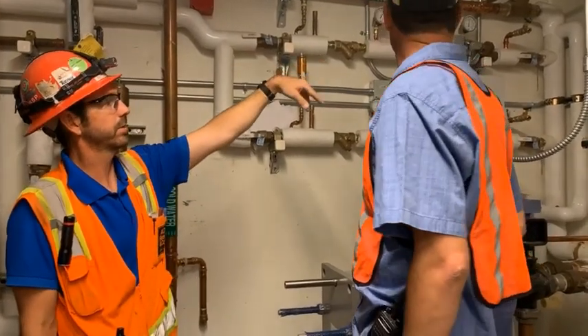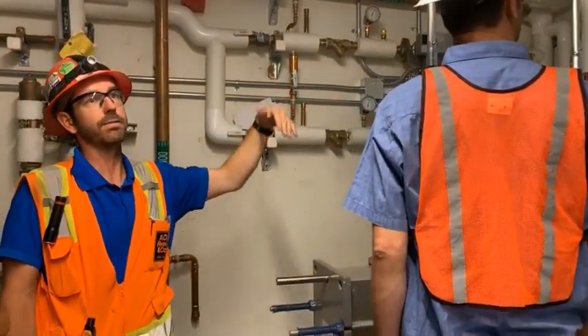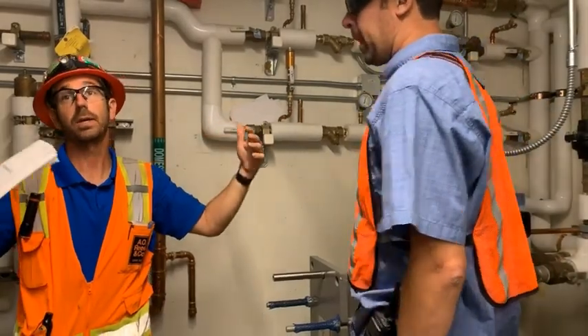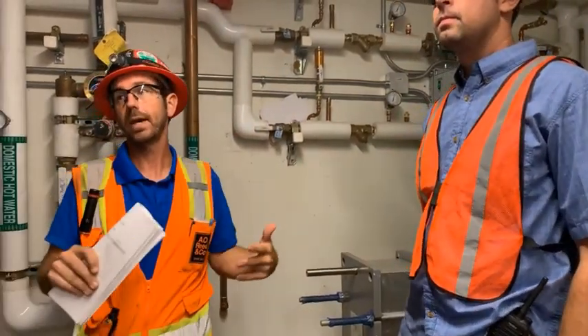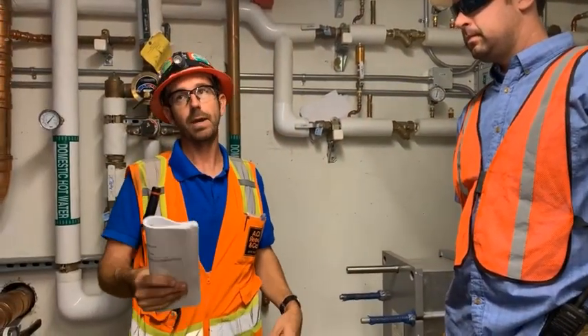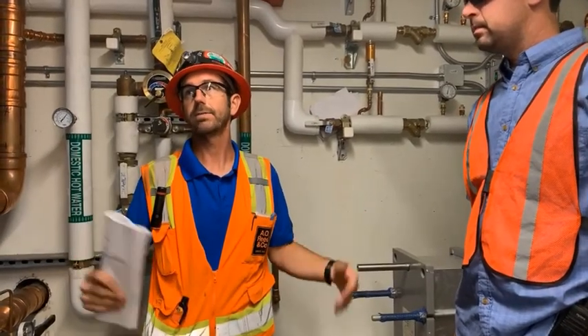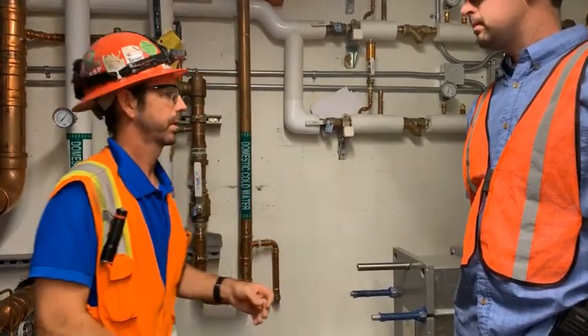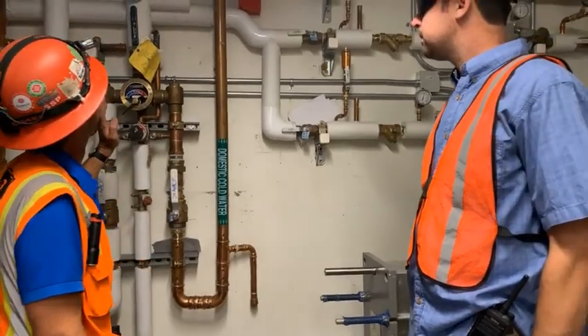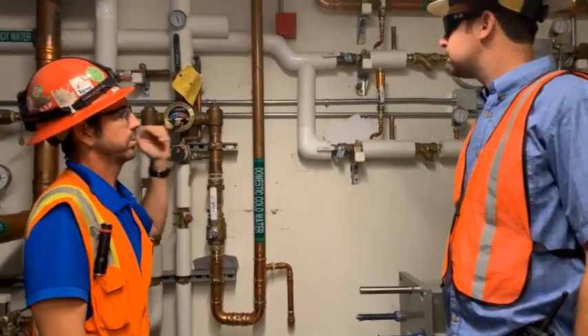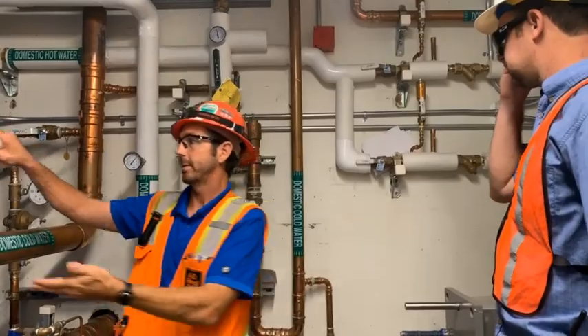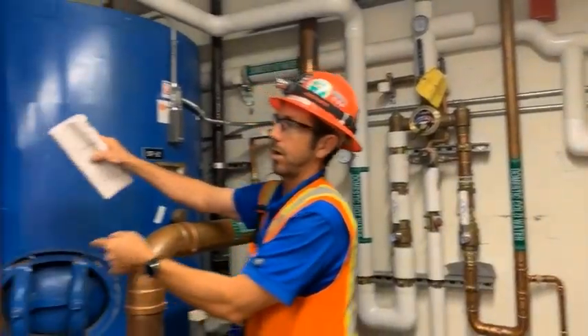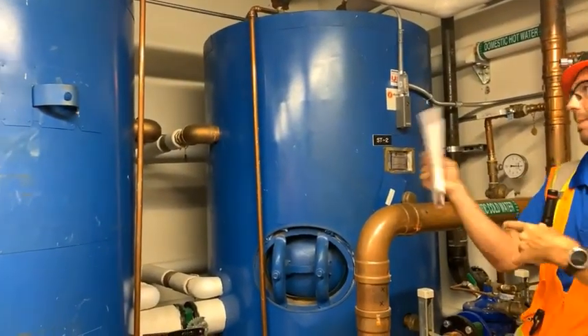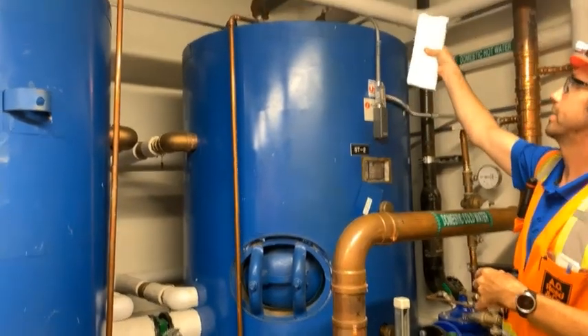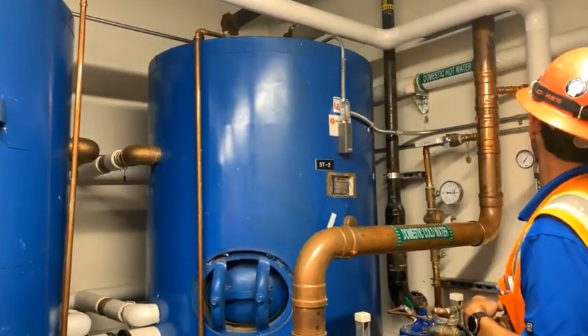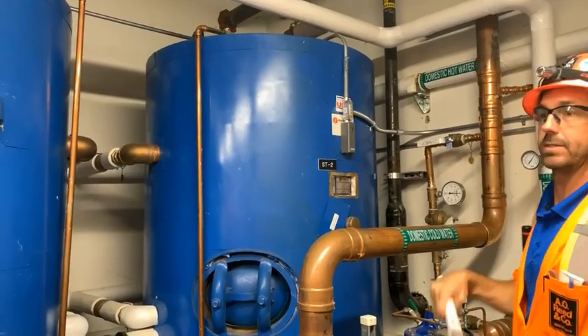For the heat exchangers, we're kind of going into HVAC stuff. A lot of this stuff now is just going to be mixed together, plumbing and HVAC, okay, because it's all intertwined. To make one loop through plumbing and then another for HVAC seems like it might be a waste of time, okay? So that's the heat exchangers. So these two pumps and the piping that's in the middle of the tank are drawing the water out of the tank through the heat exchanger back into the tank. The piping off the top is the 140 that feeds your mixing valve, okay? It only feeds the mixing valve in this building.